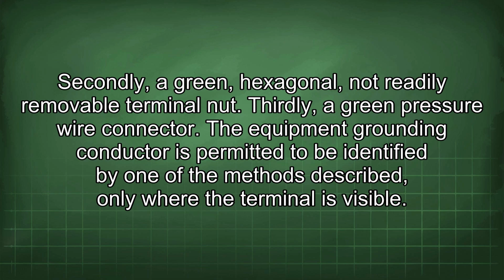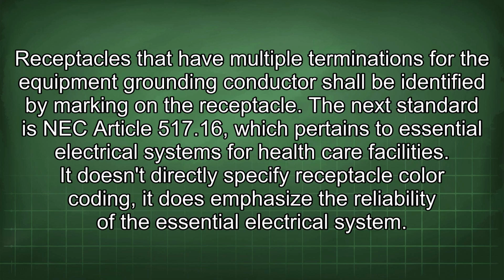The equipment grounding conductor is permitted to be identified by one of the methods described only where the terminal is visible. Receptacles that have multiple terminations for the equipment grounding conductor shall be identified by marking on the receptacle. The next standard is NEC Article 517.16, which pertains to essential electrical systems for healthcare facilities.